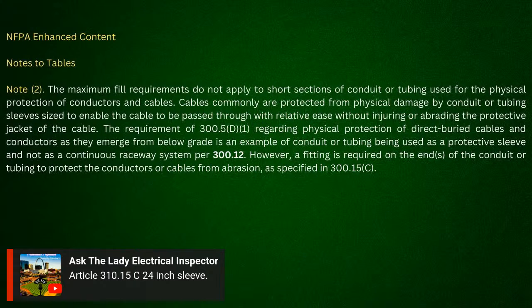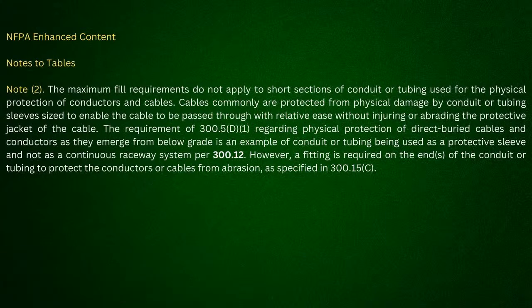310.15(C) for a 24-inch sleeve, but I think the 24-inch, wouldn't that be considered a nipple from box to box? Yes. Anything 24 inches or less is a nipple. Okay? As long as I've been doing this, we have always said that if you're 24 inches or less, it's a nipple. And I've sat there and listened to them argue over this.